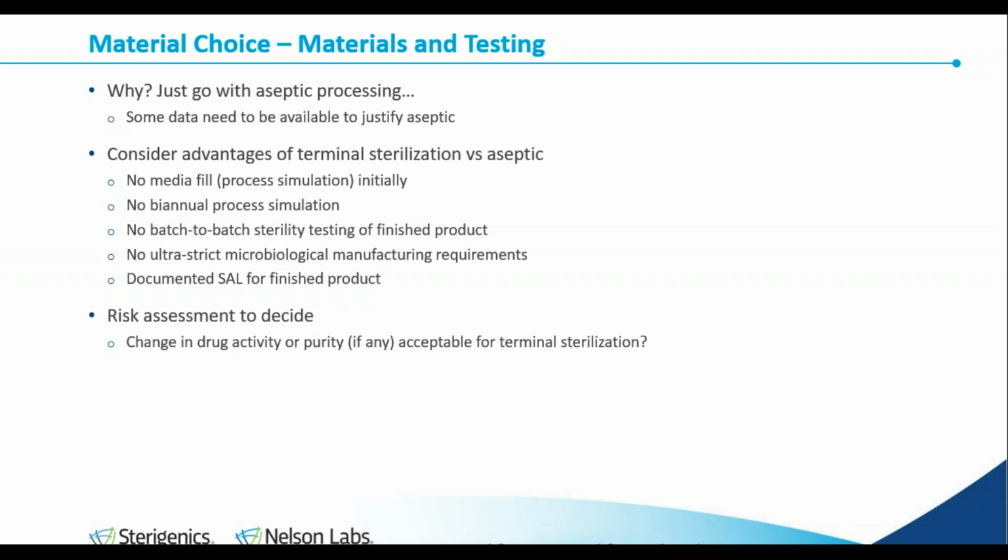But there's some real advantages to terminal sterilization, and so there's no initial process simulation or media fill. There's no biannual process simulation required. There's no requirement for batch-to-batch sterility testing. In fact, I'm going to talk more about that later.